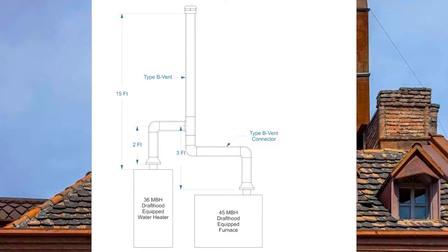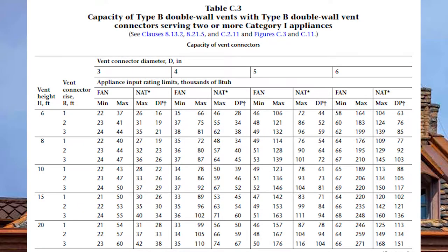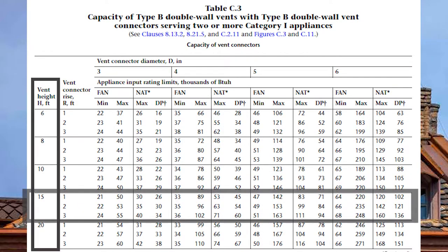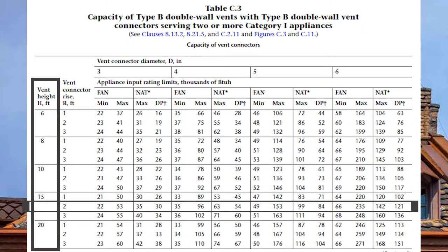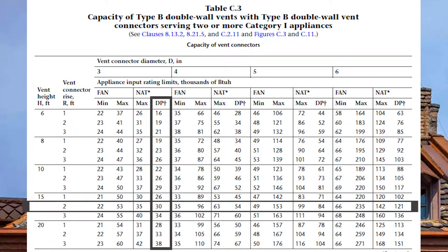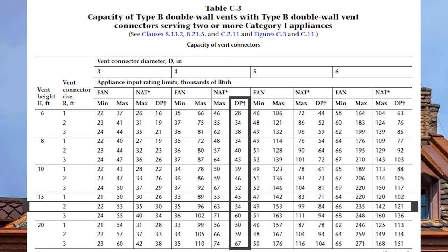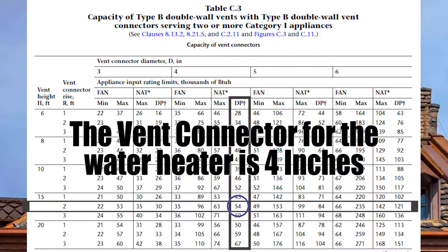Let's start with the 36,000 BTU hot water heater. Coming down on the left-hand side to the 15-foot vent height and across on the two-foot vent connector rise — this is natural draft so I need NAT DP. The three-inch area is only good to 30,000 BTUs. Moving over to the four-inch area, NAT DP is 54,000 BTUs, so the vent connector for the hot water heater will be four inches.